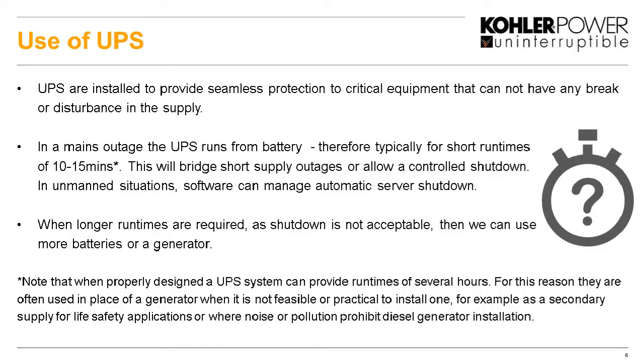So, onwards. What are the uses of UPSs? UPSs are put in where we have to provide complete seamless protection to any critical equipment, where that equipment cannot have any break at all, or any disturbance in the supply. The UPS is there as a completely uninterrupted power supply to this critical equipment, to ride through disturbances in the mains. Typical run times of a UPS are quite short, from about 10 to 15 minutes, and this would typically bridge the gap in the supply, or allow for a controlled shutdown.